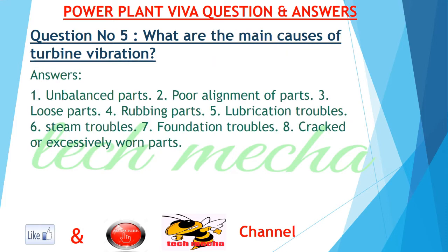Question number 5: What are the main causes of turbine vibration? Answers: 1. Unbalanced parts. 2. Poor alignment of parts. 3. Loose parts. 4. Rubbing parts. 5. Lubrication troubles. 6. Steam troubles. 7. Foundation troubles. 8. Cracked or excessively worn parts.